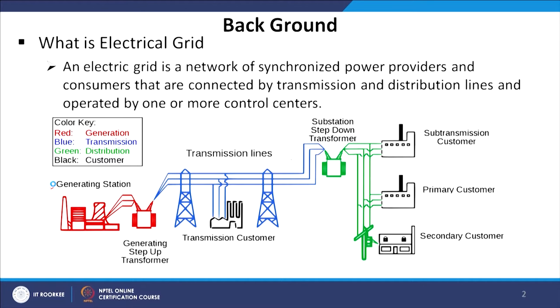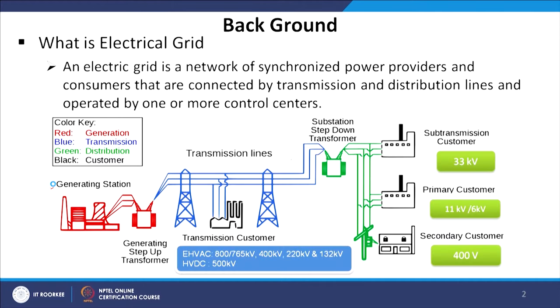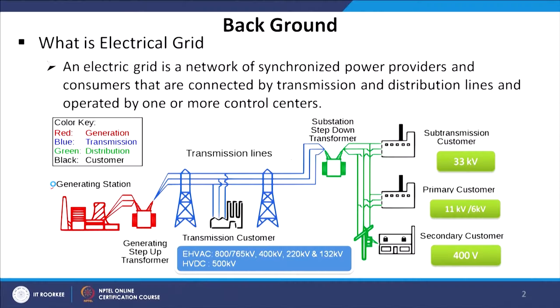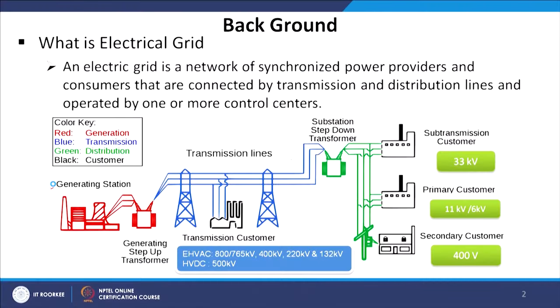The generating station ideally transfers its energy through either EHV AC lines or HV DC lines. The voltage ratings of EHV AC lines are either 800/765 kV, 400 kV, 220 kV, and 132 kV, whereas the commonly used HV DC lines are of 500 kV. The sub-transmission customers are connected at 33 kV, primary customers at 11 kV, and secondary residential customers at 400 volts.